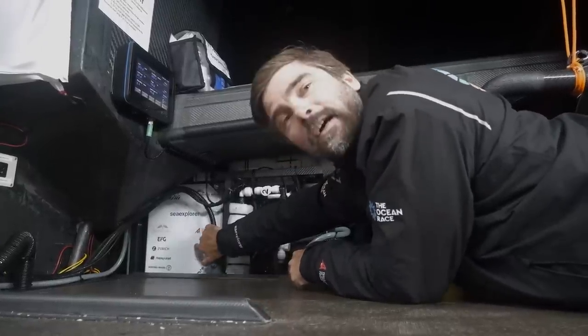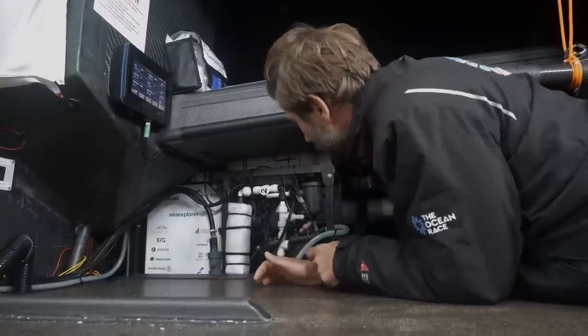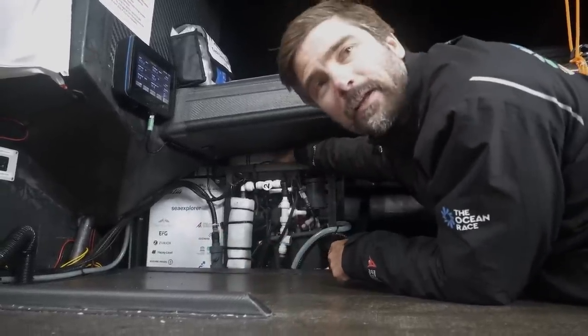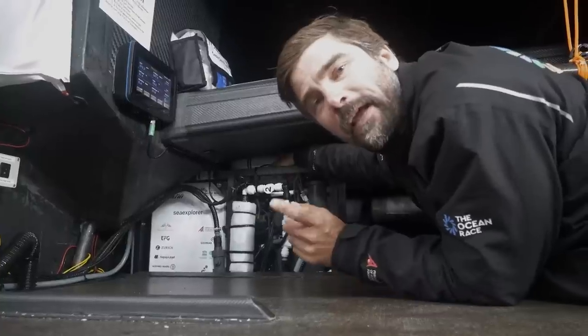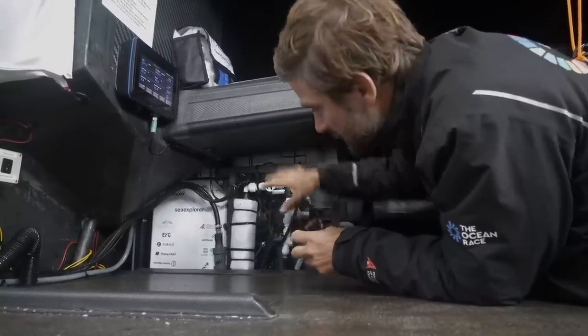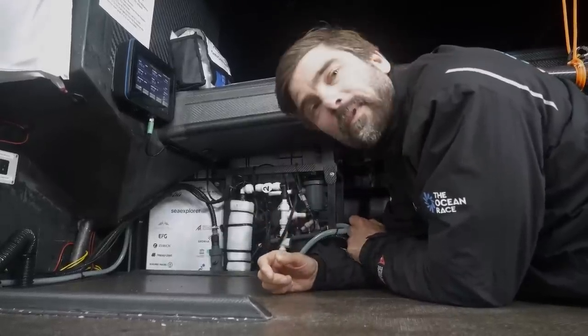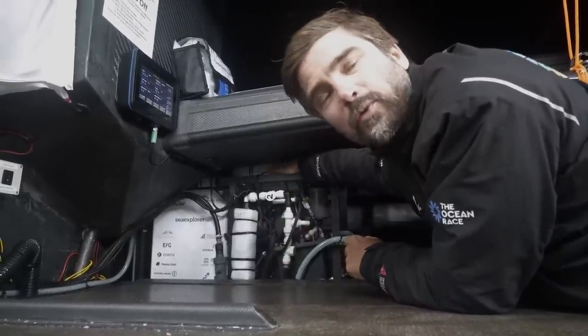In here the gas is analyzed — the gas pressure. We also have a gas bottle here, a CO2 bottle, and every day at the same time the system automatically calibrates its sensor with this pure CO2 in this bottle.